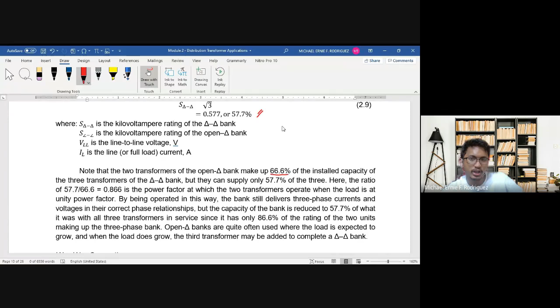Let's say we have three single-phase transformers totaling 500 kVA, each 167 kVA. If one is damaged, you have 167 times 2, which equals 333 kVA — that's the installed capacity of the remaining transformers.